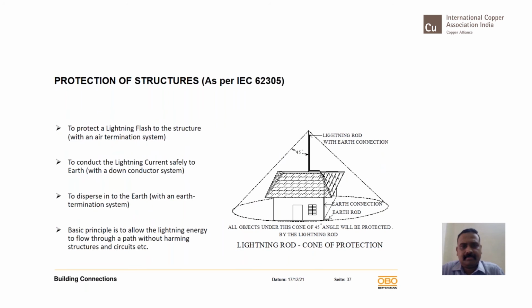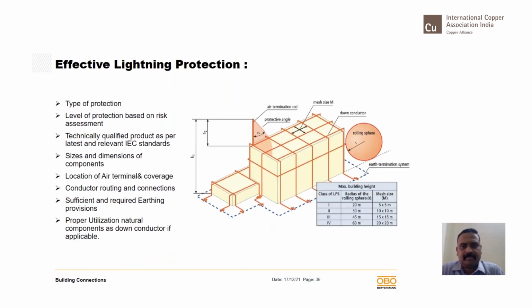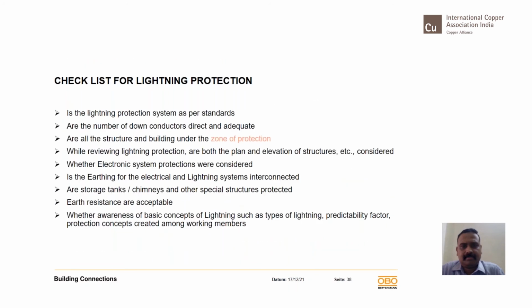So we discussed what makes an effective lightning protection system. Now, what is the checklist that you need to follow? You need to ensure the lightning protection system is as per the latest standards. Older buildings which have an existing lightning protection system might have been installed with respect to the 2309 standards which were practiced earlier. However, the new standards have a lot of changes, so this system needs to be revisited and brought in line with the latest standard.